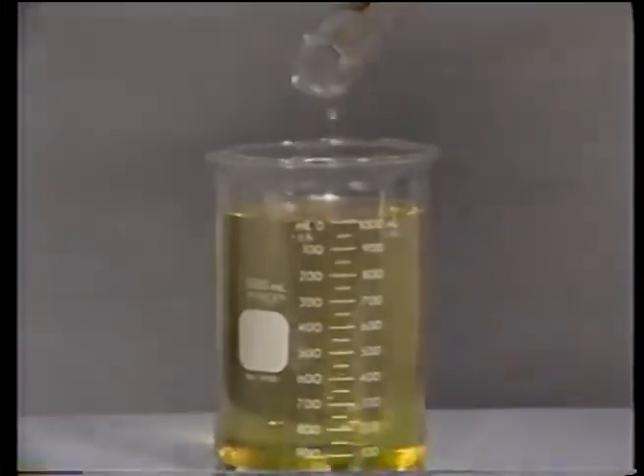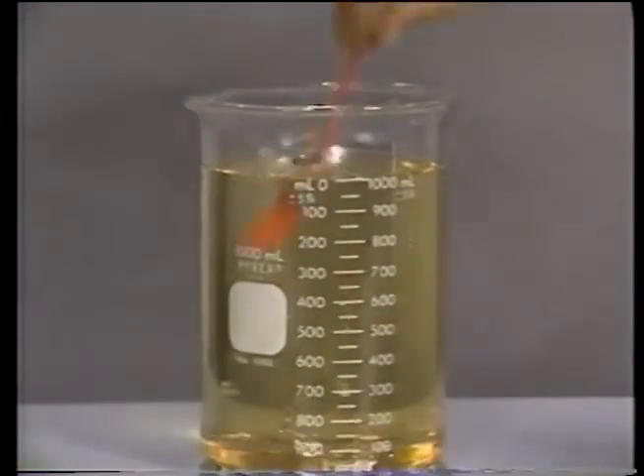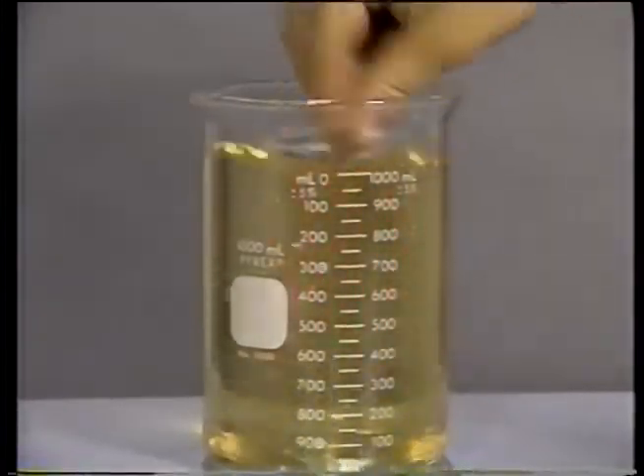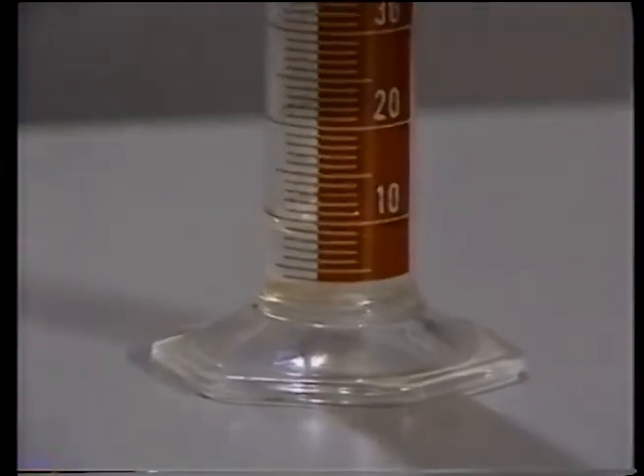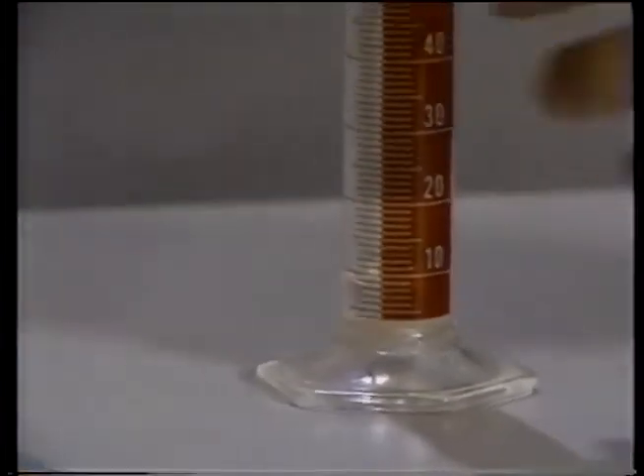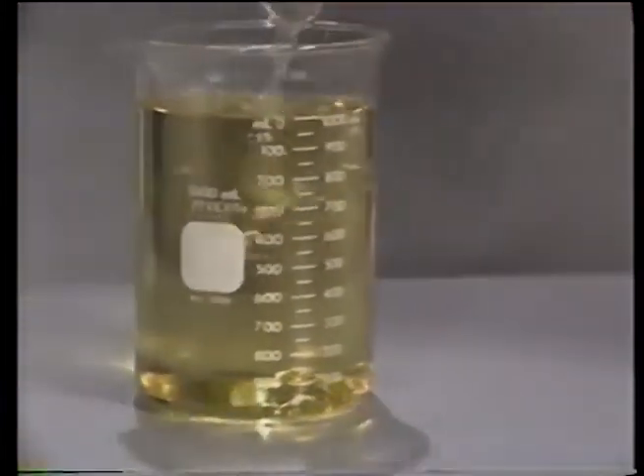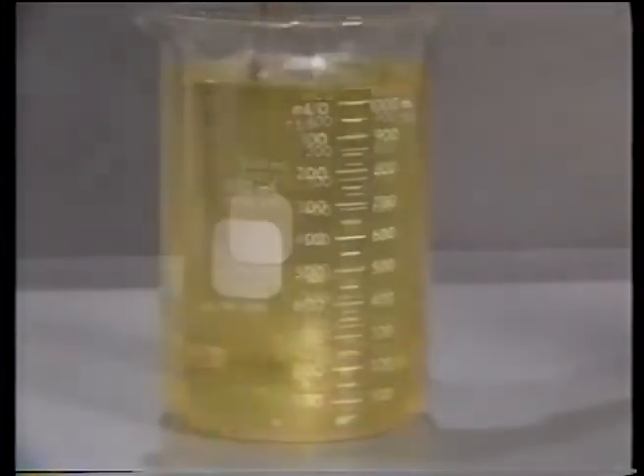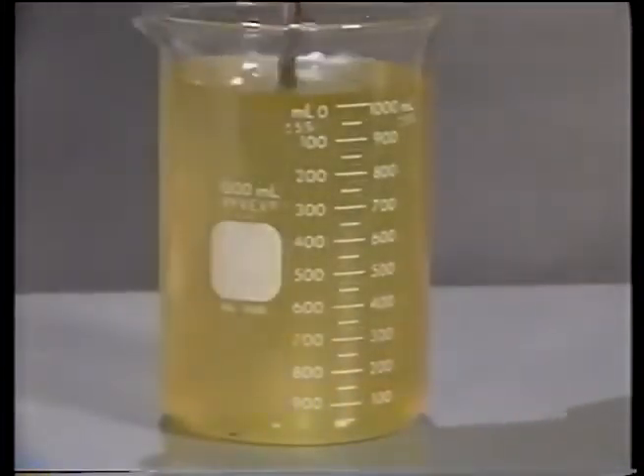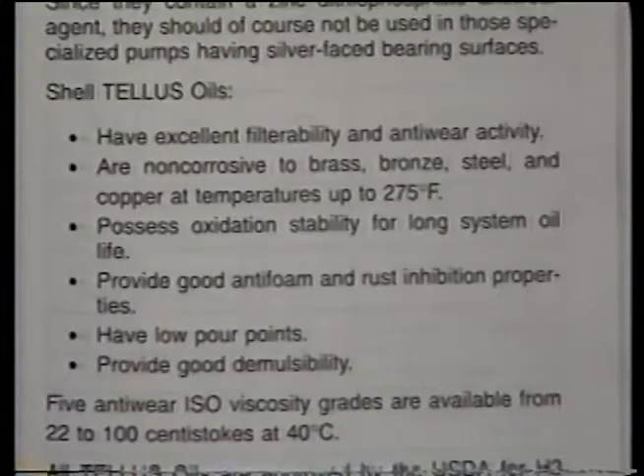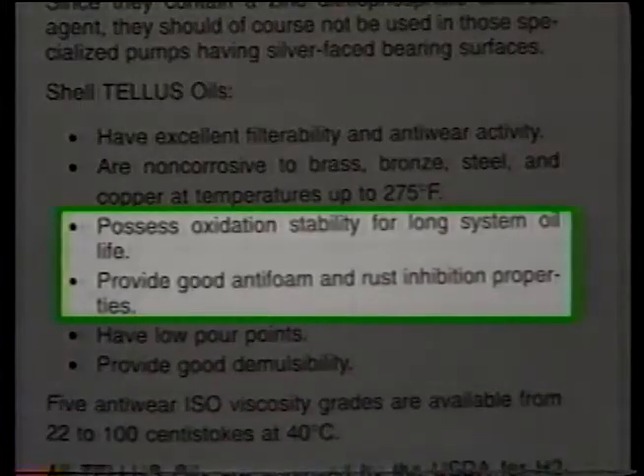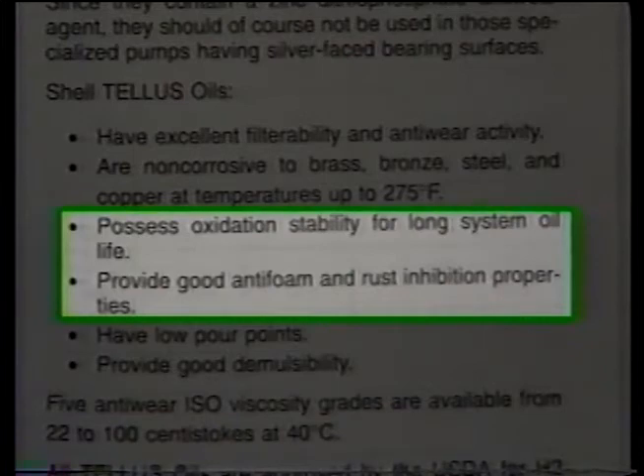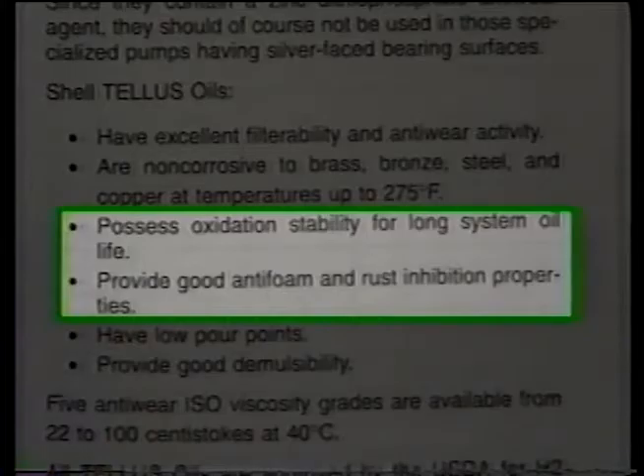However, except in critical systems, this isn't usually reason enough to discard the oil. If the water content is one percent or more, the oil will look milky. Oil manufacturers often add a rust and oxidation inhibitor to the oil. The rust inhibitor coats the metal surfaces of the system with a chemical film and retards rusting.